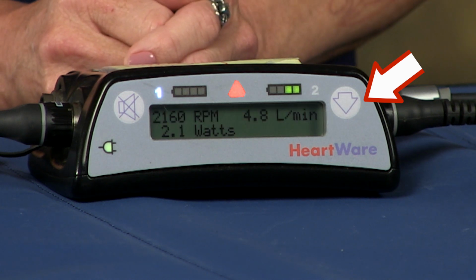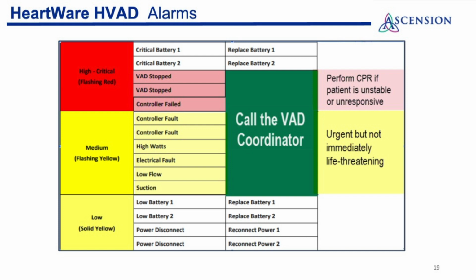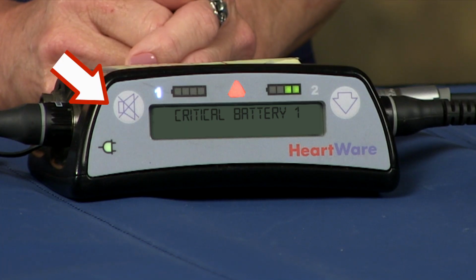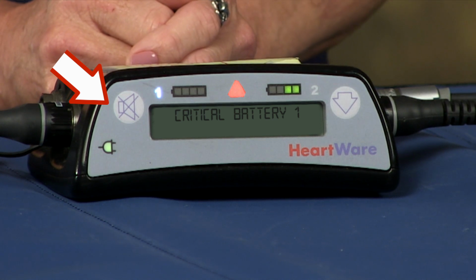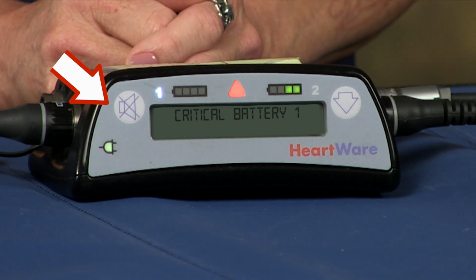If any alarm is not being tolerated, defibrillation and/or CPR may be necessary. The HeartWare HVAD has extremely loud alarms if the condition is a high priority, meaning potentially life-threatening. So here is where the alarm silence button is located, so you can focus and hear the VAD coordinators when they are trying to help you troubleshoot. Remember, assess your patient first.